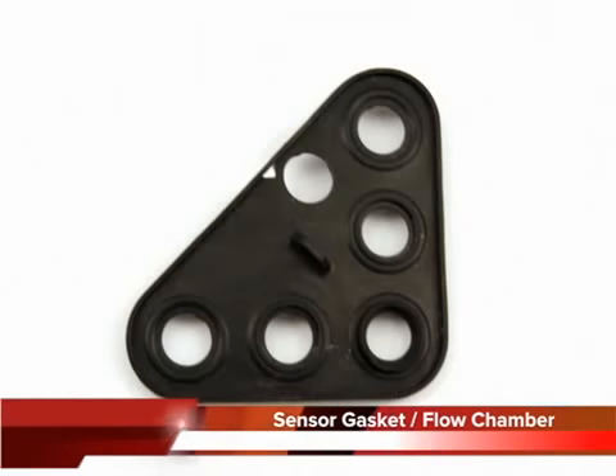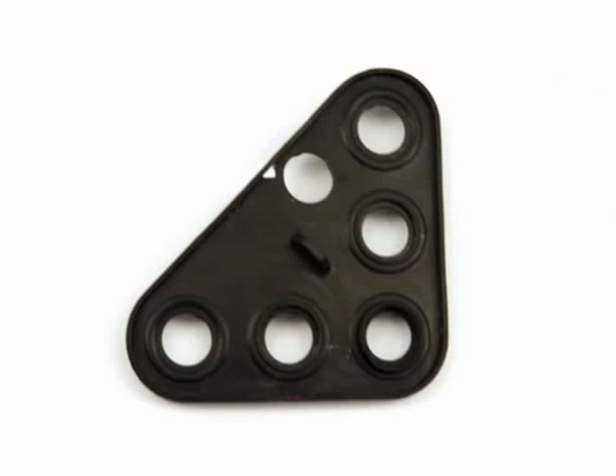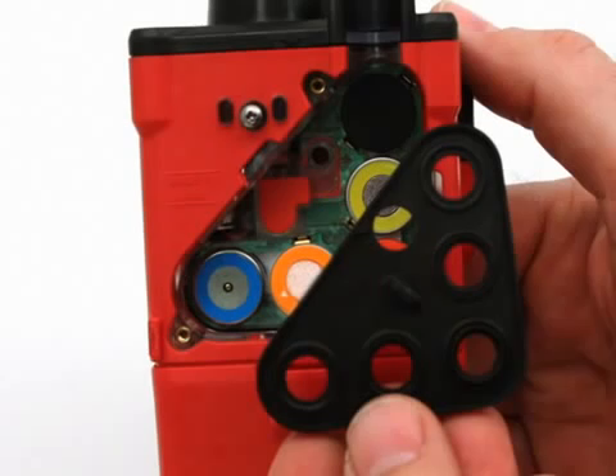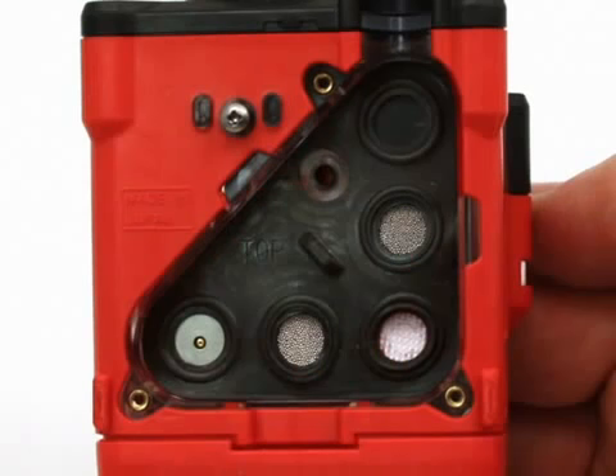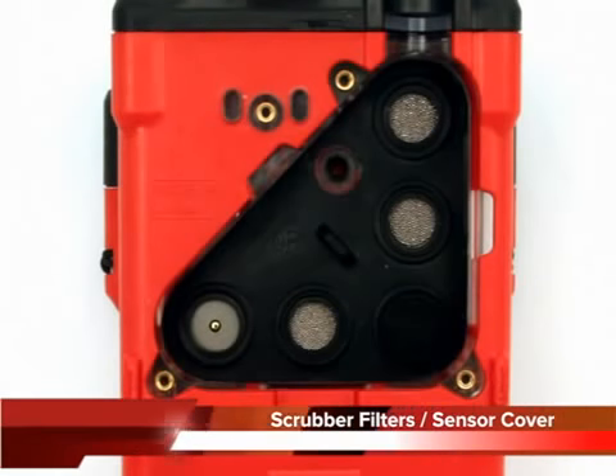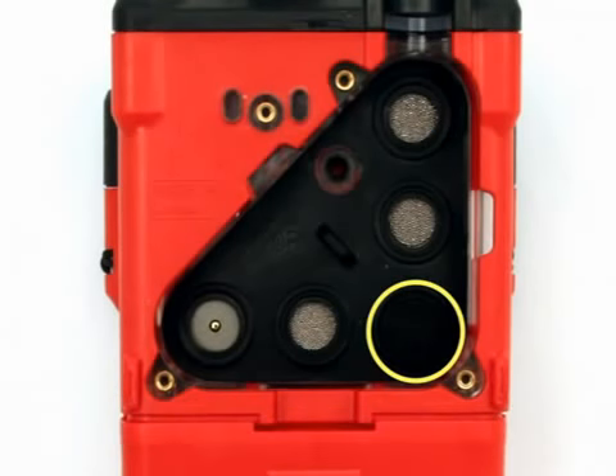The sensor gasket seats onto the sensors and seals the interface between the sensors and the flow chamber. The flow chamber sits on top of the sensor retainer. 3 screws secure the flow chamber to the case. The charcoal filter disc is located in a recess in the sensor gasket just above the CO sensor. It is black, has a woven texture, and is impregnated with a hydrogen sulfide absorbing material. It fits into a recessed area of that port.